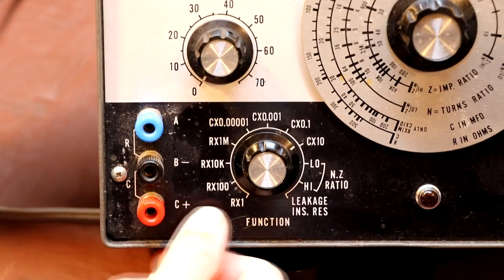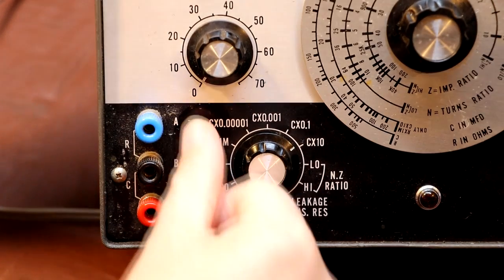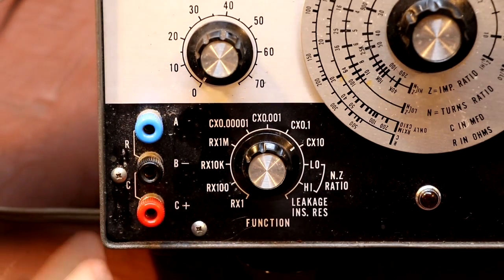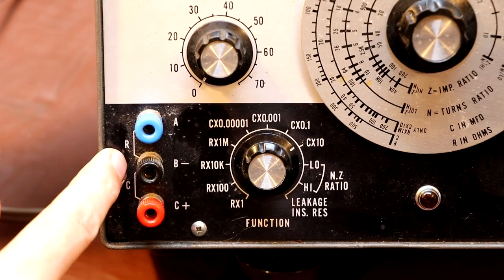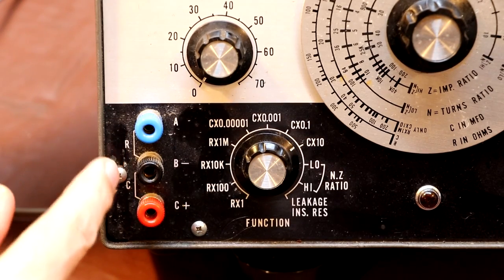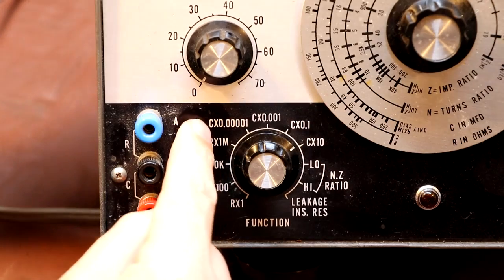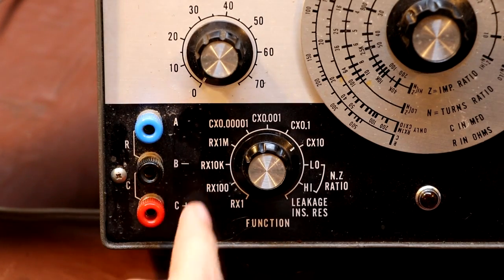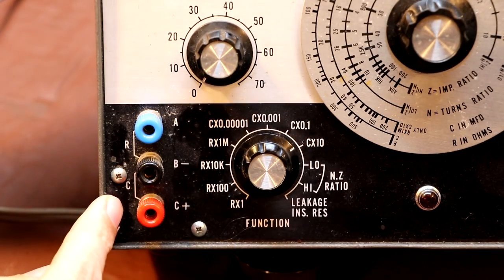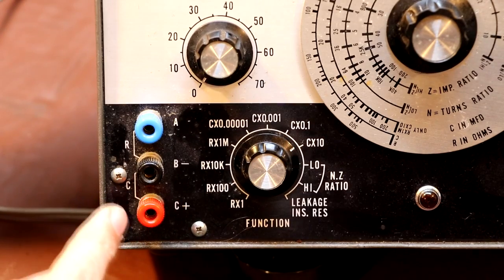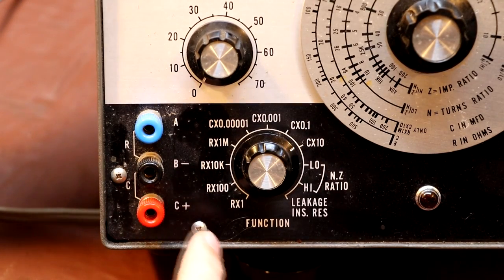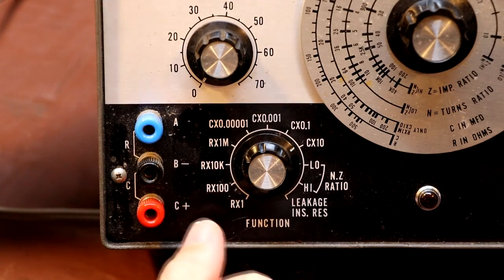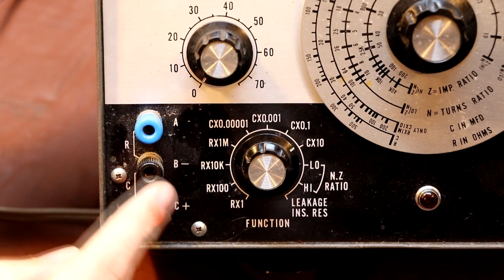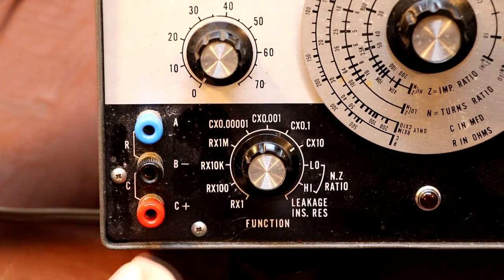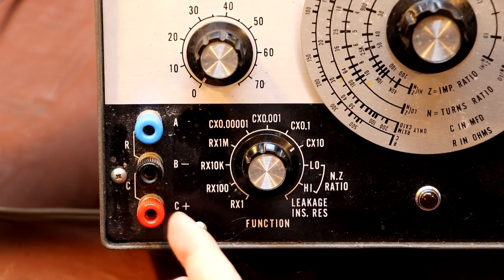So on the front of the instrument we've got 3 terminals labelled A, B and C, and it's got a little link drawn on the side here which shows that for measuring resistance you use the top two terminals, which is A and B, and for measuring the capacitance values you use the bottom two terminals, which is B and C. And actually the B has got a minus on it and the C's got a plus on it, and again the two bottom terminals are colour coded black and red.